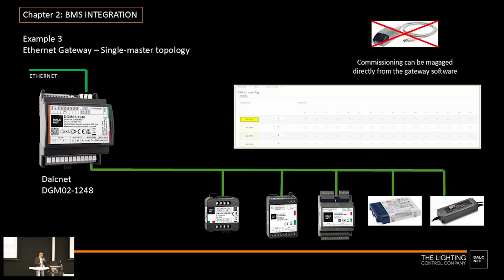For example, the DGM02 added DT8 functionality to this kind of device. But DT8 commands mean you are controlling RGBW or tunable white DALI products. You need to have some logic behind it, and it's not so direct or easy to convert the same signal on the Ethernet side. It requires a bit of knowledge on the protocol and how DALI works.